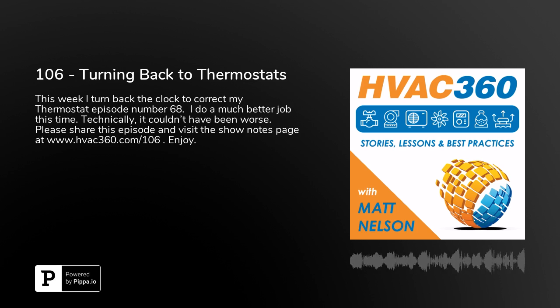And so what you have is the potential to do both heating and cooling. The logic will dictate exactly what mode it should be in. The user doesn't have to define what mode it has to be in. The logic in the device will identify what mode it has to be in by the set point that you give it. So for example, if you set it to 70 degrees and it drifts down to 68, and that might be your heating set point. So if you have a plus or minus 2 degrees, it goes down to 68, it'll start turning on at 68, and it'll go all the way up until 70, and then it'll shut off.